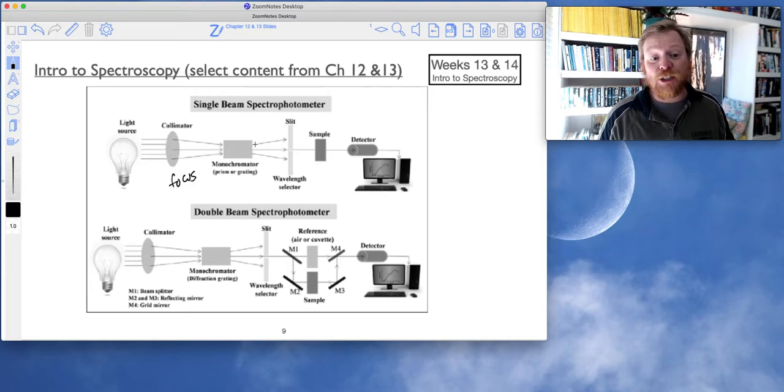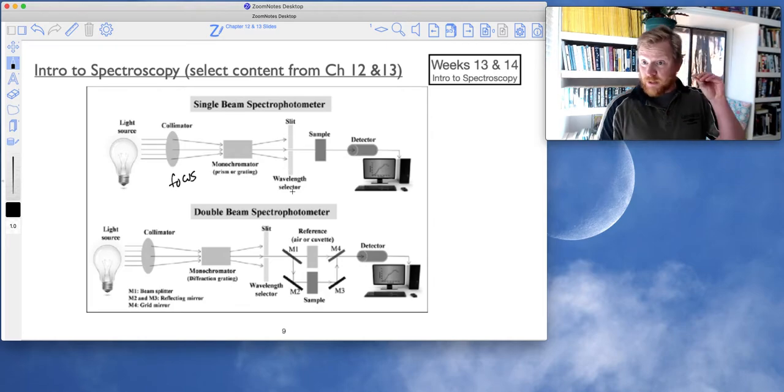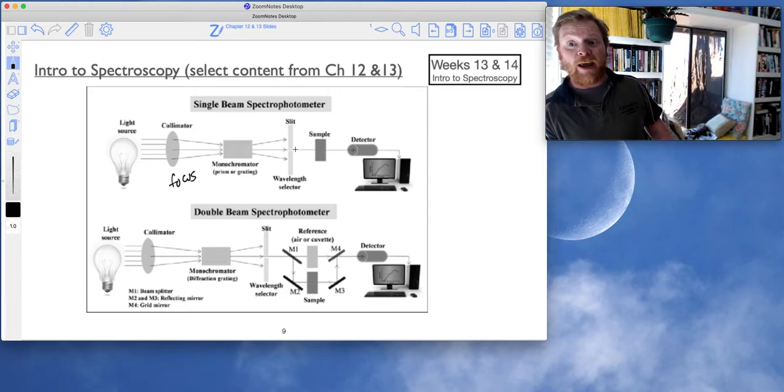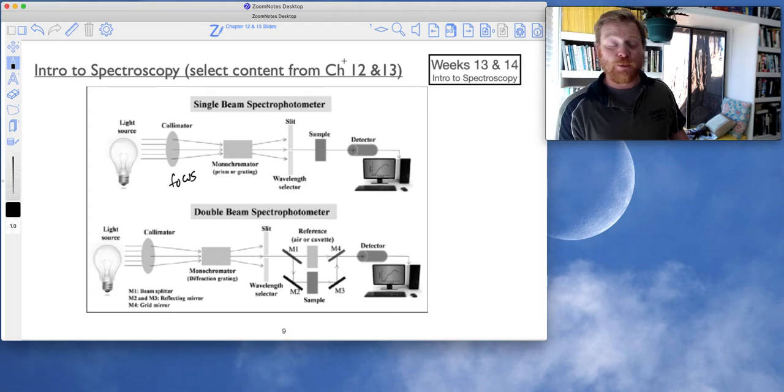And that diffraction grating might come out divergent. So we'll use another slit to diffract the beam into a nice tight collimated path so that it can pass over our sample and go onto our detector. And so now I know that all of you are familiar with this. When you want to get an actual spectrum, you would first take a single beam of your background, and usually the software records it.